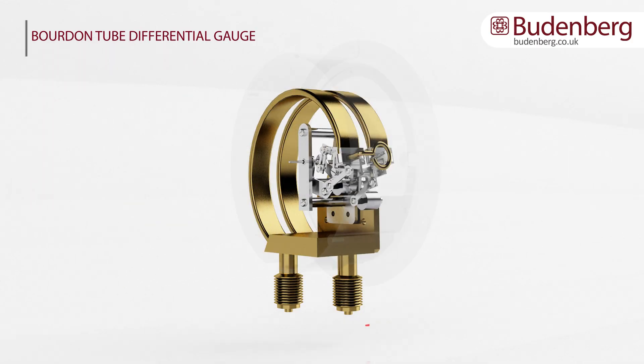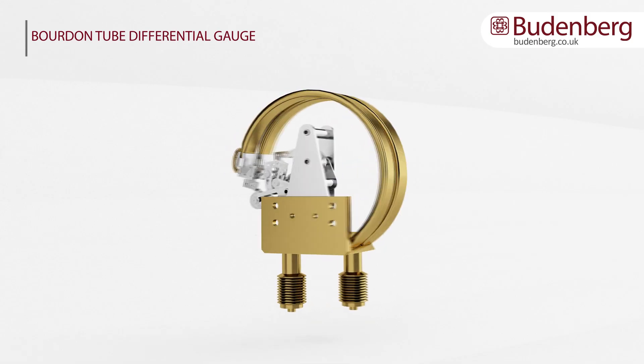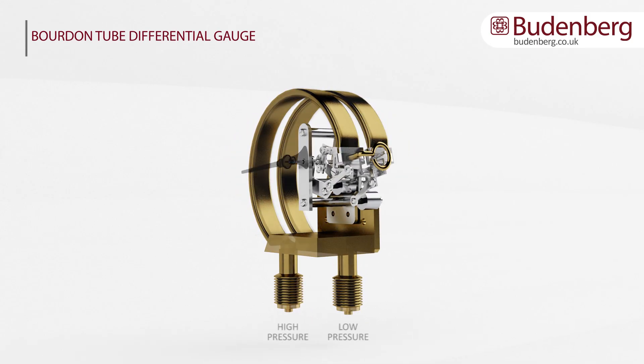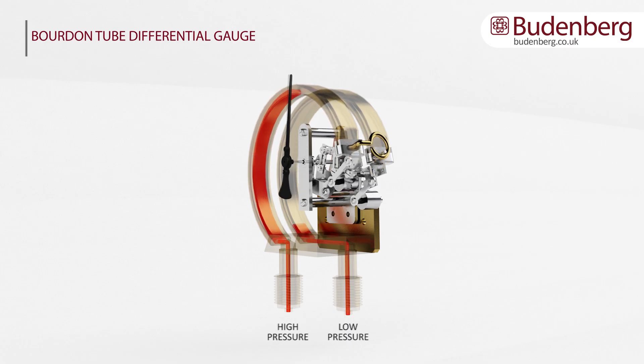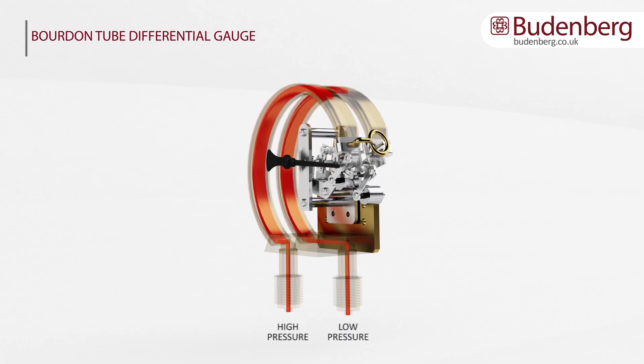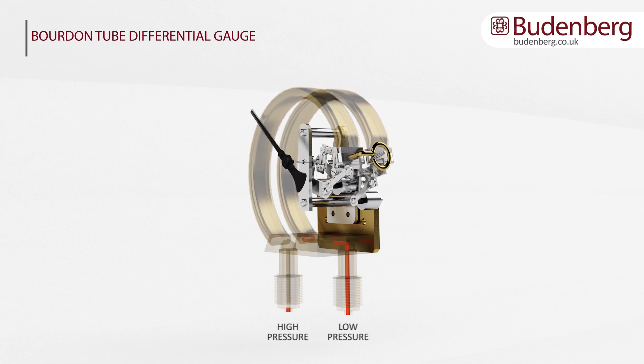The inside of a differential Bourdon pressure gauge is composed of the typical components you would expect in a pressure gauge. The main difference is that a Bourdon tube differential gauge consists of two Bourdon tubes which, when subjected to pressure, act independently measuring either the high pressure or low pressure flow.